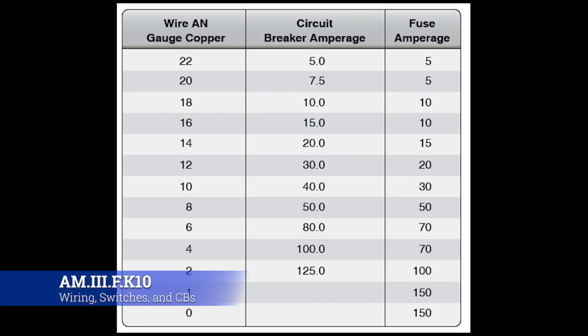Just a little bit on wire protection devices. These are things like your fuses, fuse blocks, circuit breakers, that sort of thing, anything that protects your power plant or appliance from a high amperage condition. If something gets grounded out, the amperage goes through the roof, and the circuit breaker will pop to keep it from starting a fire, blowing stuff up, or both.